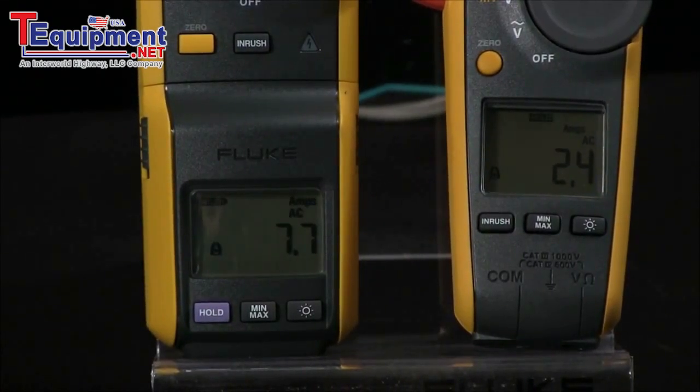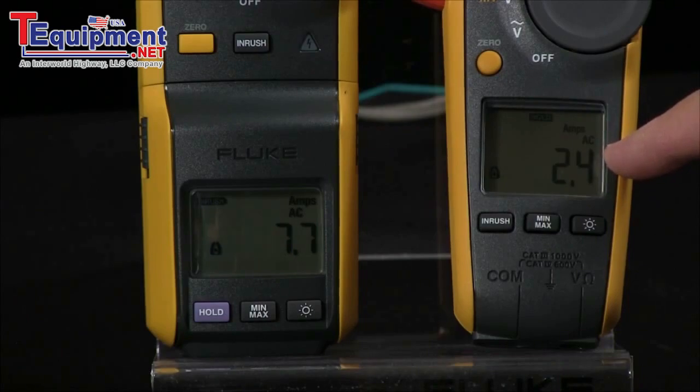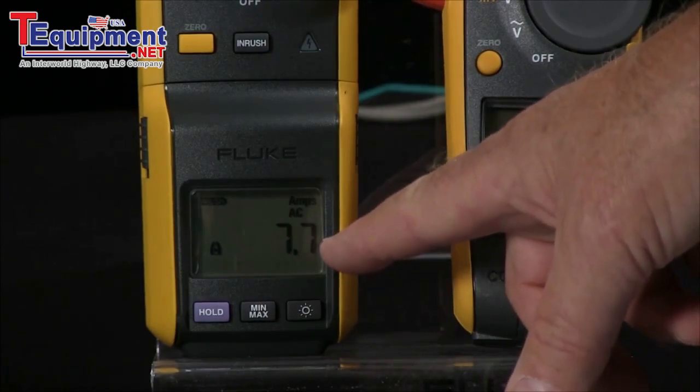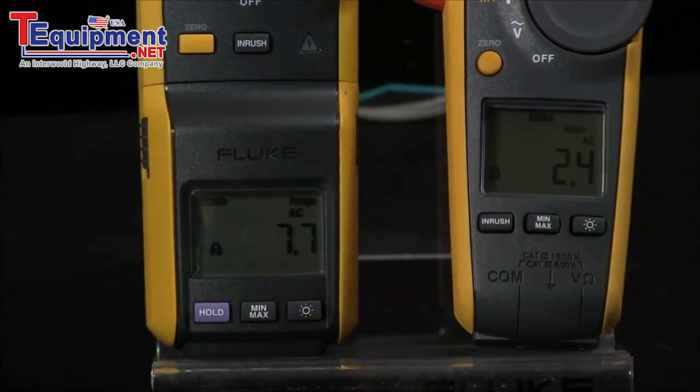Now you see typically people would think the starting current might be only two times the running current, but it's actually four to ten times the running current on a motor. So it's very important to know that this is happening.